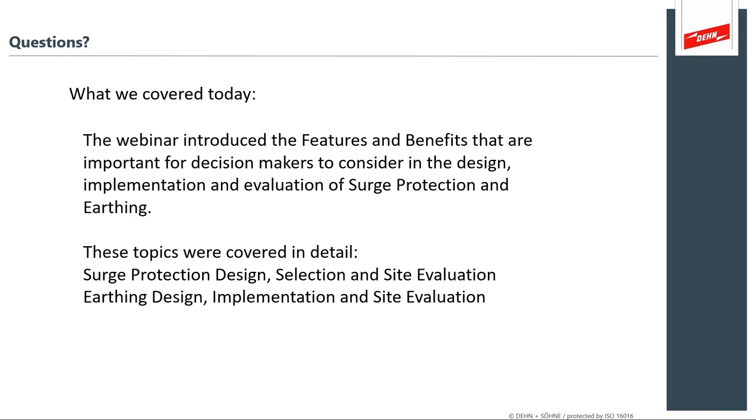I would just like to address this last question. Addressing maintenance on SPDs. The person is asking, what type of maintenance schedule should he put in place for the surge protection devices he has installed? So SPDs generally do not last forever. Metal oxide varistors do degrade over time, and it's sort of a double question. How often are you being struck by lightning? How often are you experiencing problems on your site?